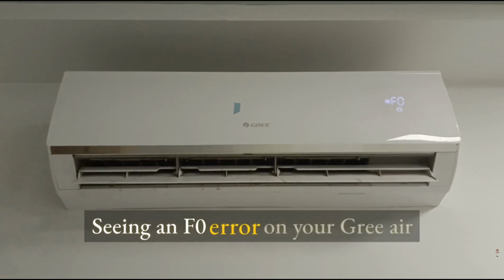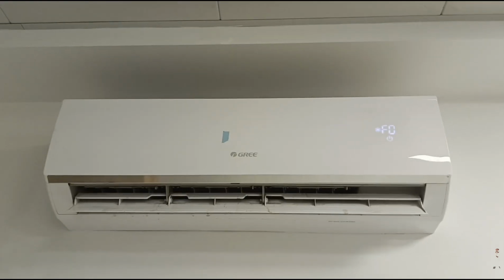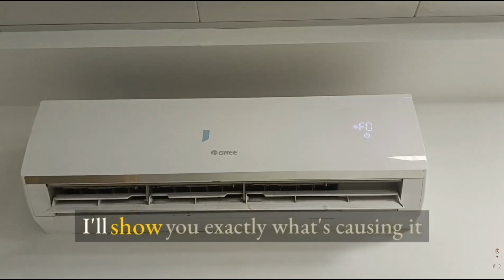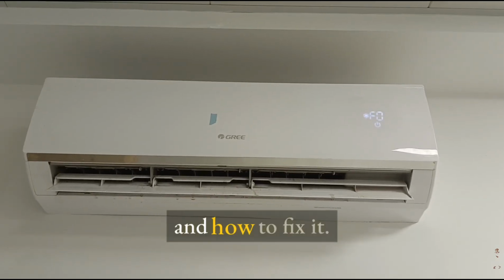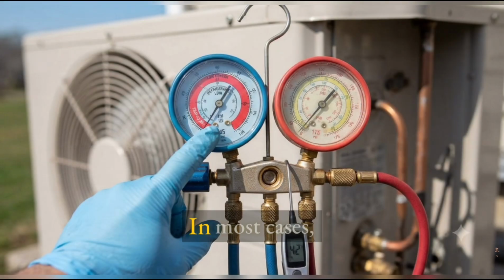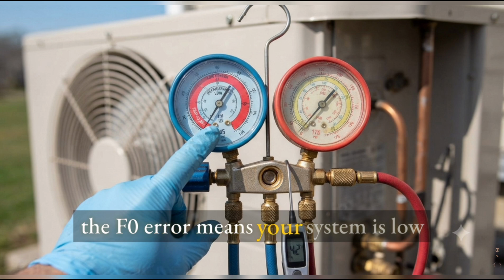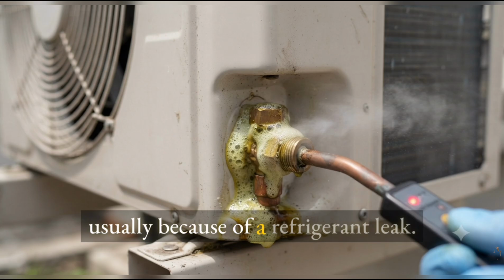Seeing an F0 error on your Gree air conditioner? Don't worry. In this video, I'll show you exactly what's causing it and how to fix it. In most cases, the F0 error means your system is low on refrigerant, usually because of a refrigerant leak.